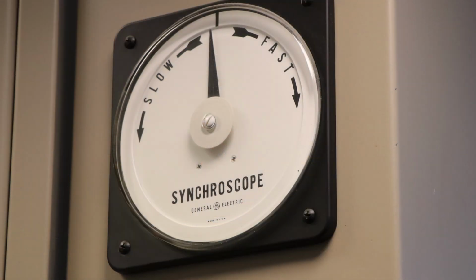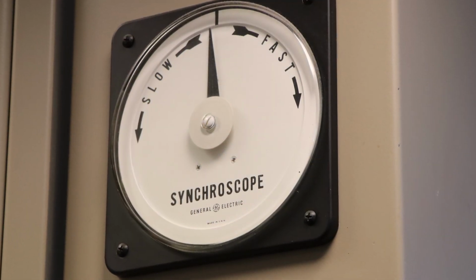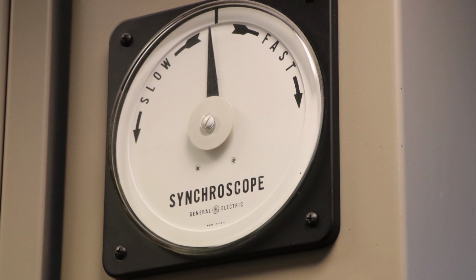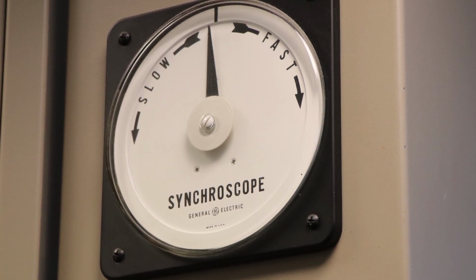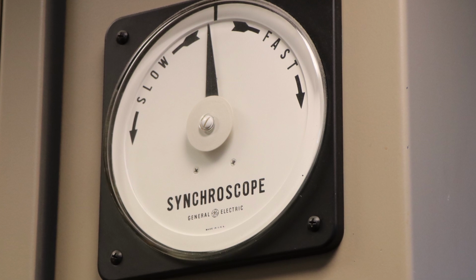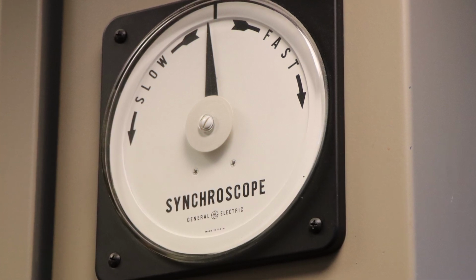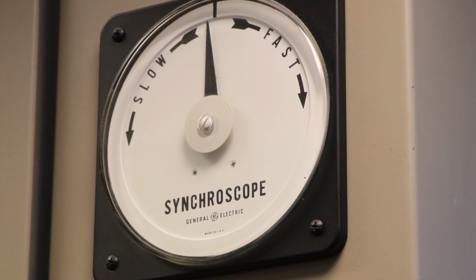How do we tie them together? Man, that's a tough one. You can't just take one generator and increase or decrease the frequency, right? Now we have our own grid - Seattle City Light is its own grid and BPA is a separate grid. So the way they actually put those together is, we have sync scopes. A sync scope is watching the system at a breaker at one of our substations where we tie to another utility. And they actually have a procedure to trip load offline or increase load to change the frequency of our system to match the other system.